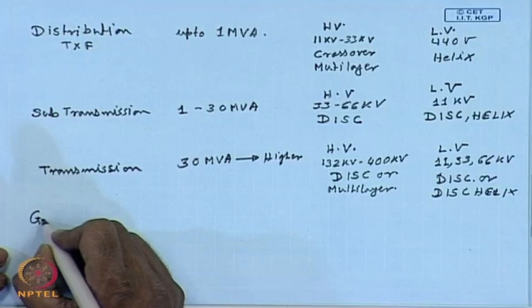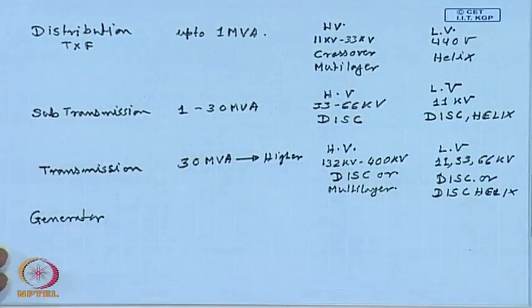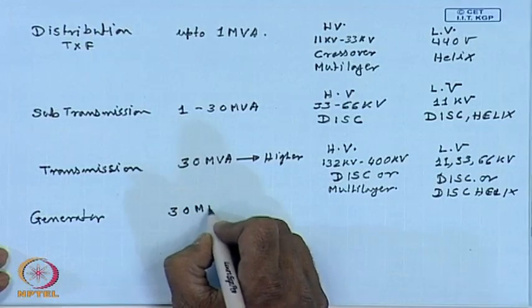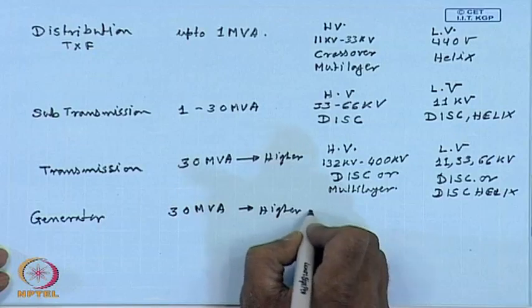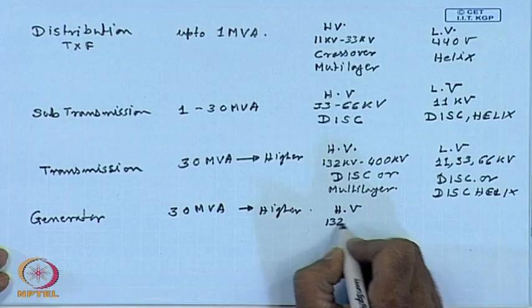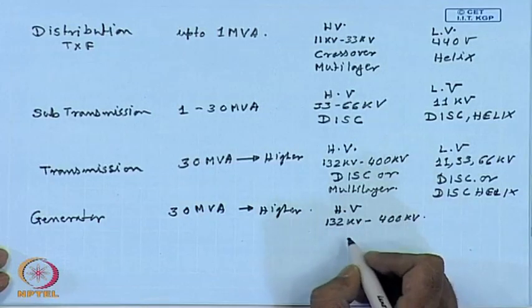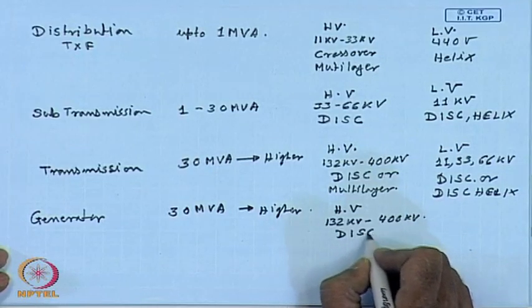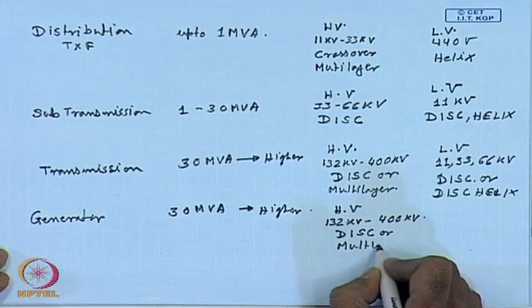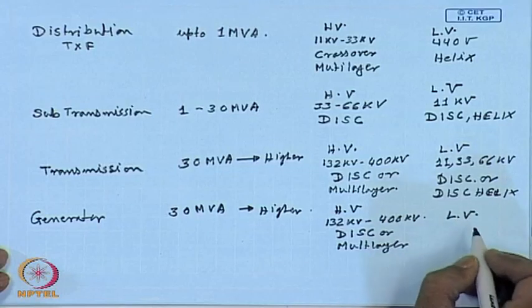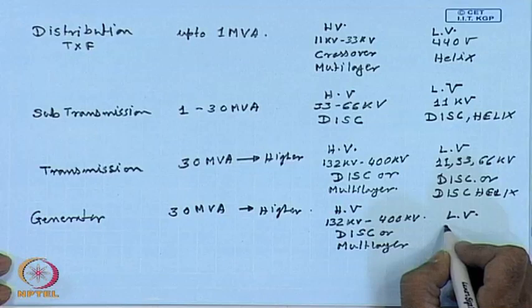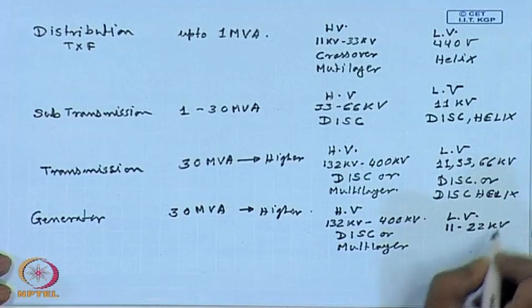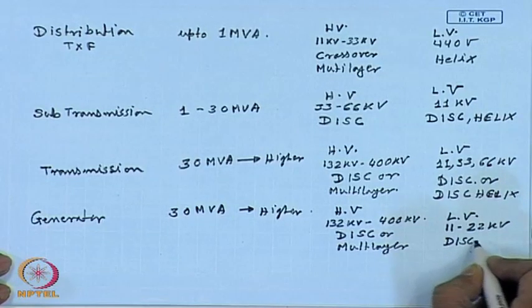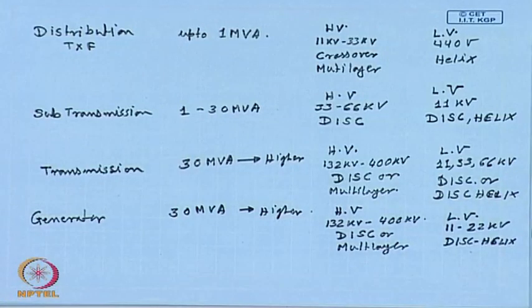Coming to generator transformer. This is also 30 MVA or upwards. The HV side is again 132 kV to 400 kV, and the choice is disc or multi-layer. The LV voltage is the voltage generated by the generator, which will be in the range of 11 to 22 kV, and the choice of winding is disc helix. So, this is a rule of thumb, but depending on the special application a particular type of winding is chosen.